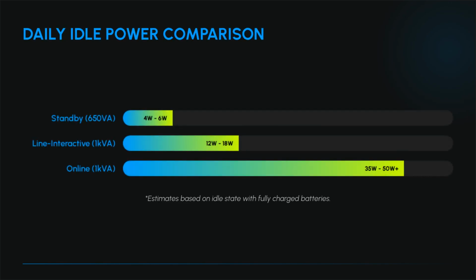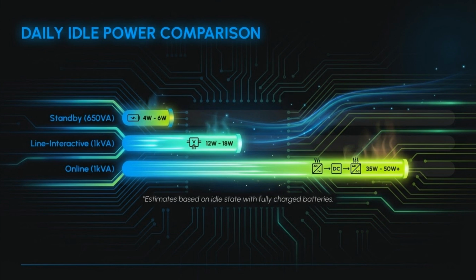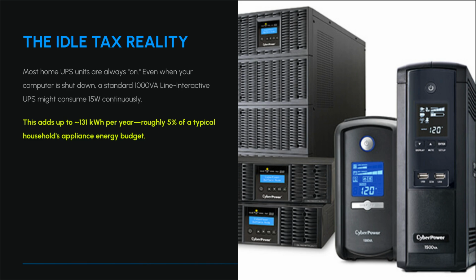Comparing daily idle power reveals large differences. A 650 VA standby unit uses 4 to 6 watts. A 1 kVA line interactive unit uses 12 to 18 watts. A 1 kVA online unit consumes 35 to 50 plus watts. These estimates are based on the UPS being idle with fully charged batteries, showing the baseline power required just to maintain readiness. The idle tax reality is that most home UPS units are always on.